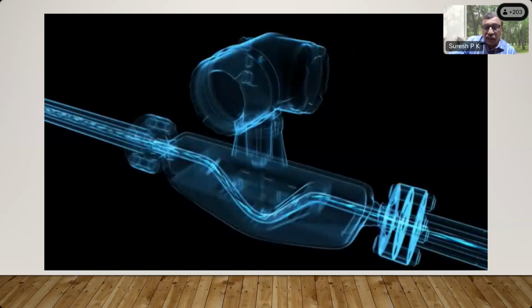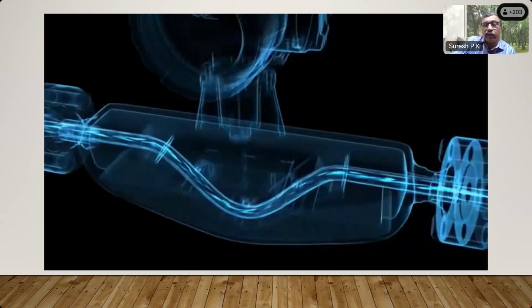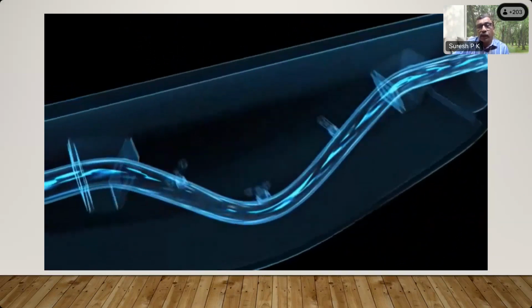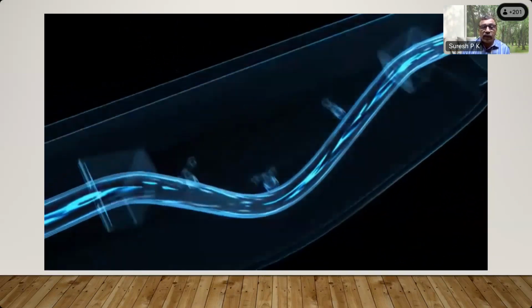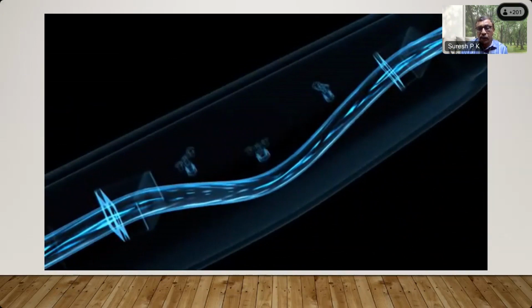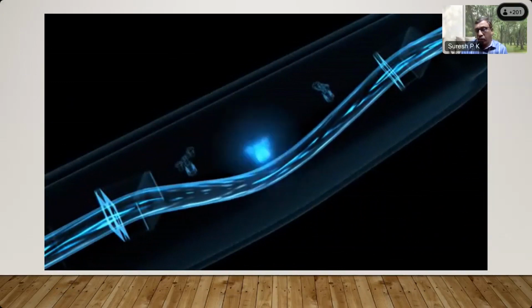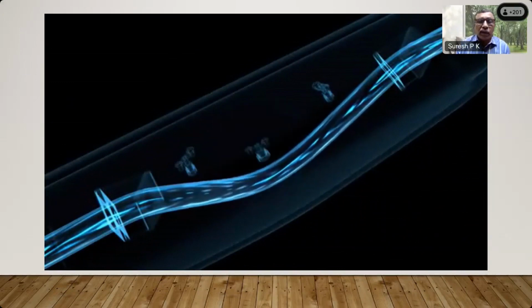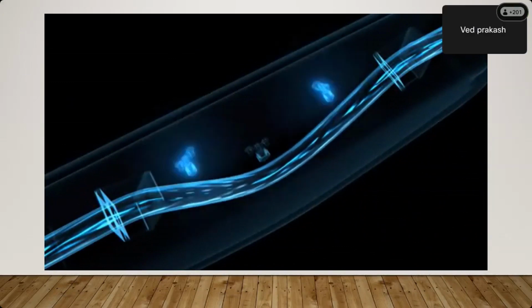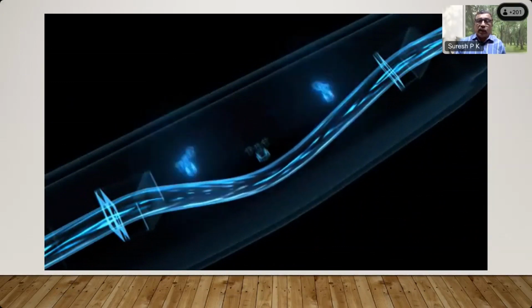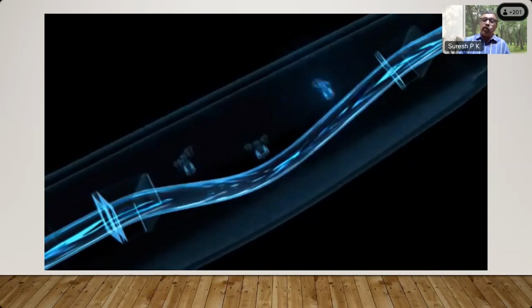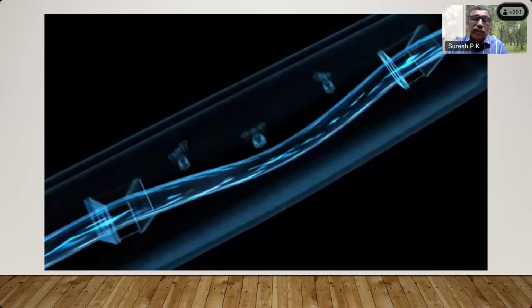So this is the inside. Something similar to this is the inside of a mass flow meter, a single tube mass flow meter, in which there is no flow taking place right now. The tube is made to oscillate using some technology, some electromagnetic force. In an oscillating tube, when the flow takes place, the tube experiences the Coriolis force.